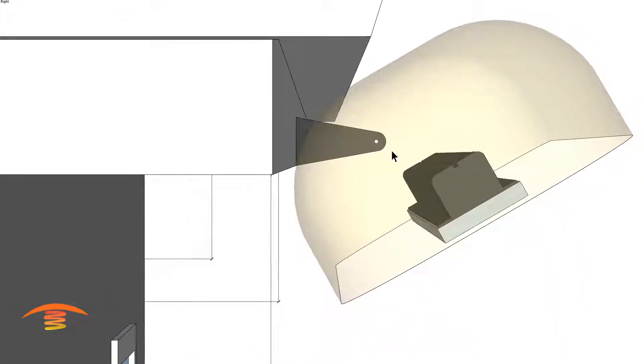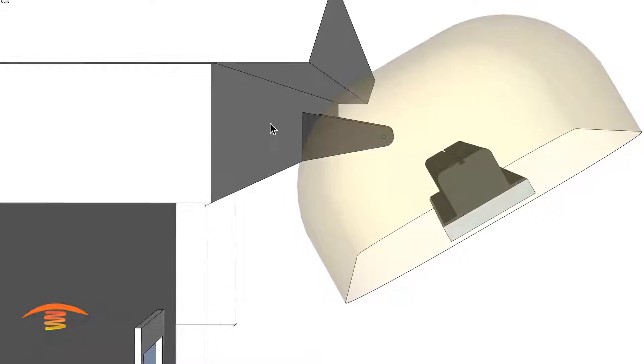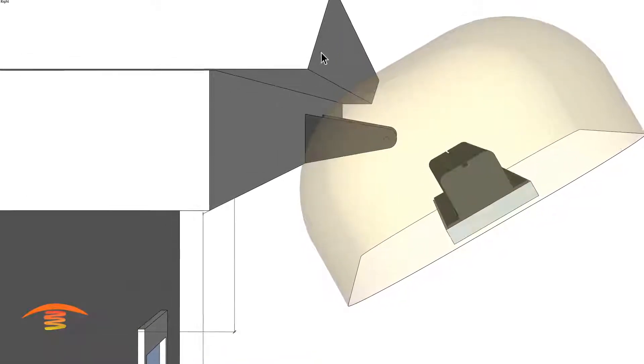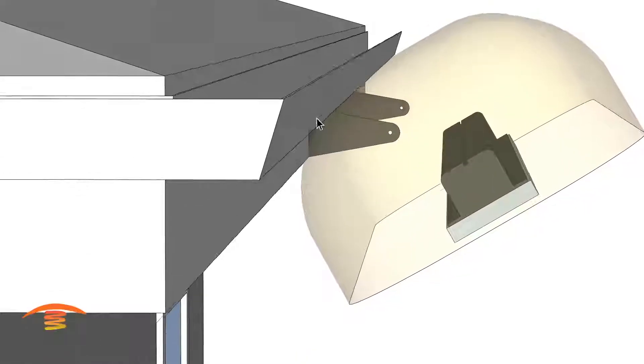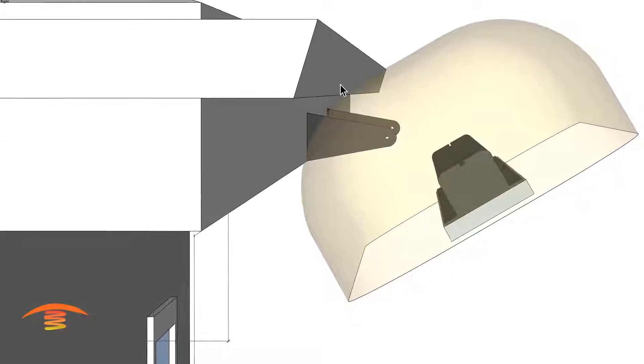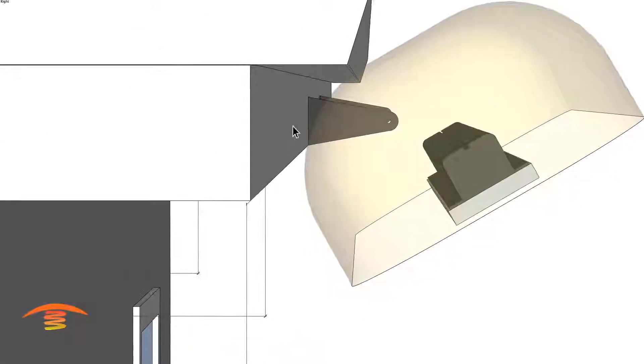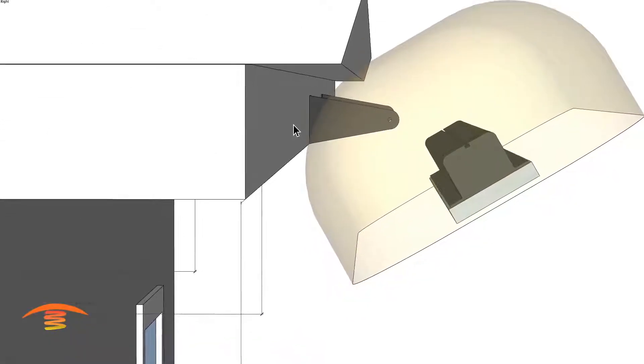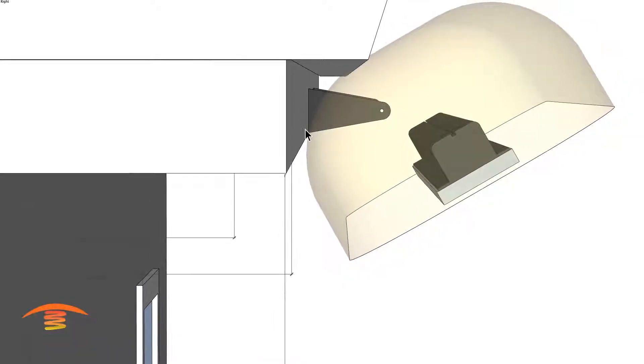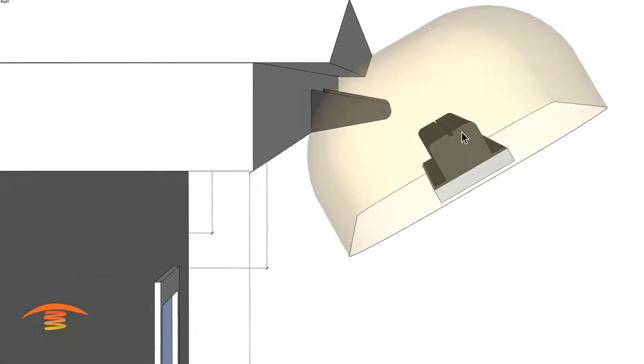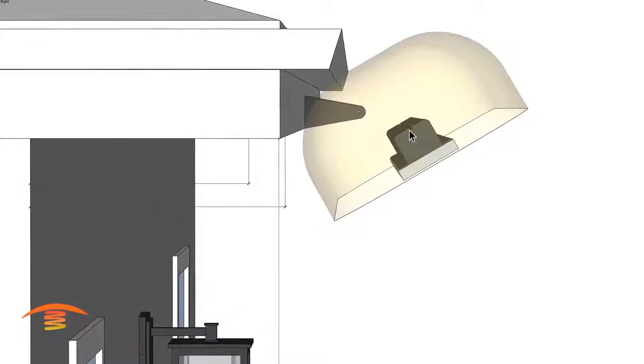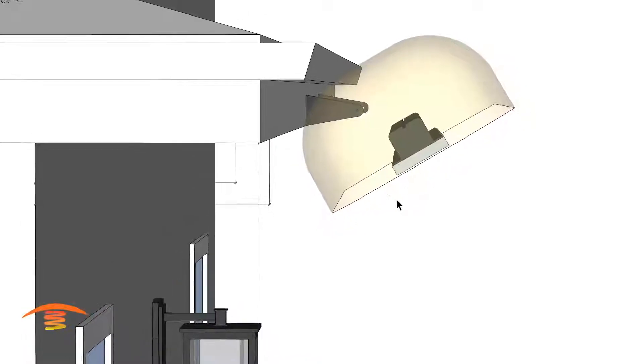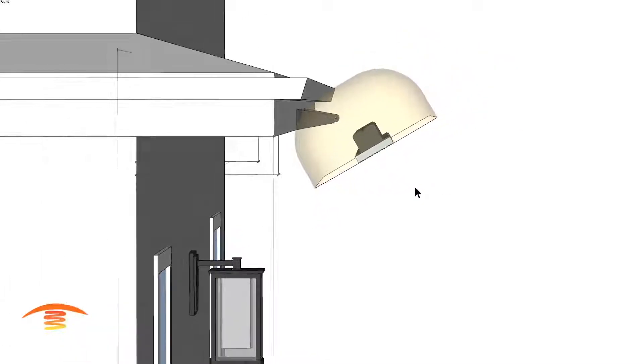But as you can see here with this clearance to combustibles, this fascia being the combustible, this is the gutter system here. And so that's non-combustible, but so we're concerned about this right here. With this combustible surface, we have to push this heater out further if we're going to angle it down to this maximum 60 degree tilt.